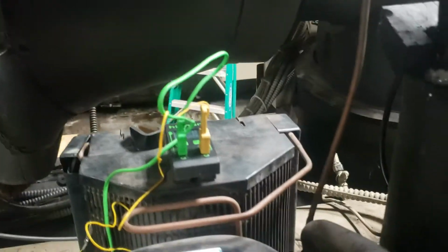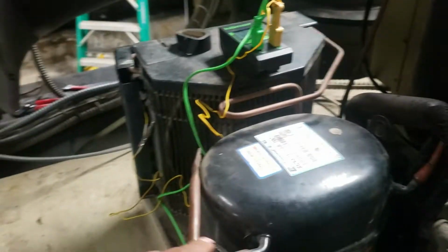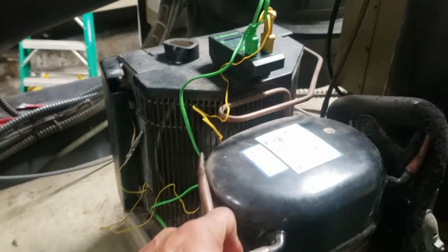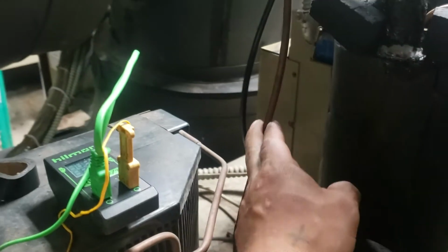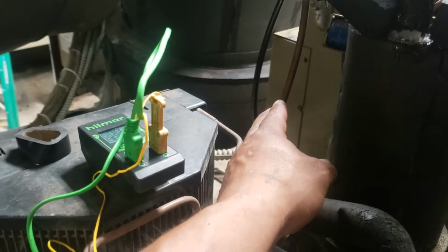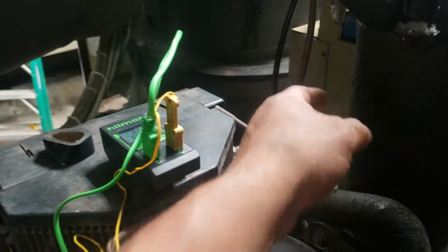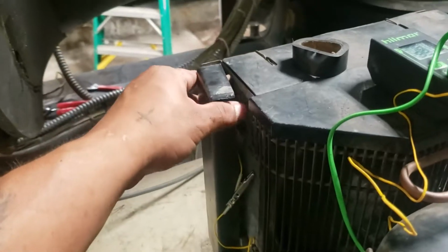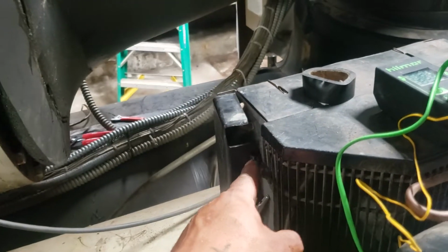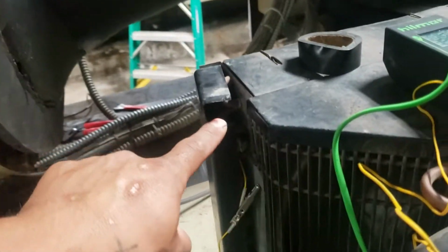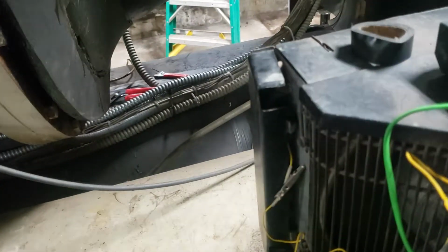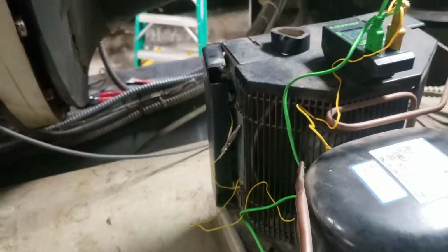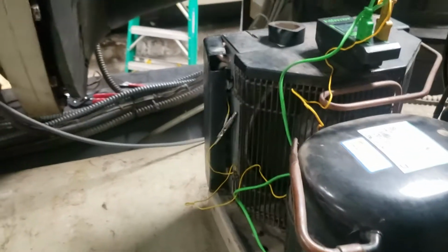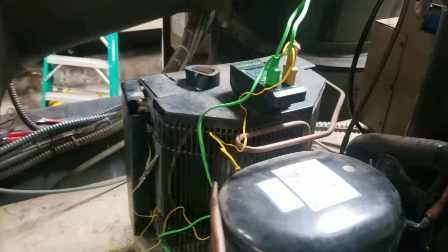So what I did, to make sure that we got the proper charge on this little small Purge unit, I'm taking a subcool reading. I took a measurement right here, my liquid line temperature coming out of the condenser, and I was at 81.6. And according to the manufacturer, they want you to take a temperature on the second or third U-bend opposite of the discharge line over here. So that's where I'm getting my temperature over here. And I got a temperature of 89.4. But so that gives me a subcooling of 7.8.